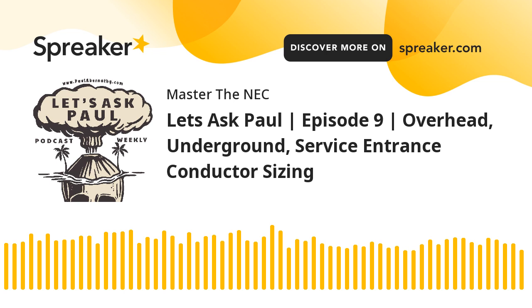Right now it says a set of fuses shall be considered all the fuses required to protect all the ungrounded conductors of a circuit. A single pole circuit breaker grouped in accordance with 240.15(B) shall be considered as one protective device. So key thing here for the person that asked the question, we size the conductors based on our loads. We determined whether it was service conductors or service entrance conductors. We follow the rules for sizing. Now we have to have at least overcurrent protection on those. But in our case, we're only going to be able to apply what? Overload protection. Now, the breaker is still going to be overcurrent protection, because that breaker is going to protect downstream faults, short circuits, things like that. But as far as the conductors on the line side, really all we're going to get here is overload protection.